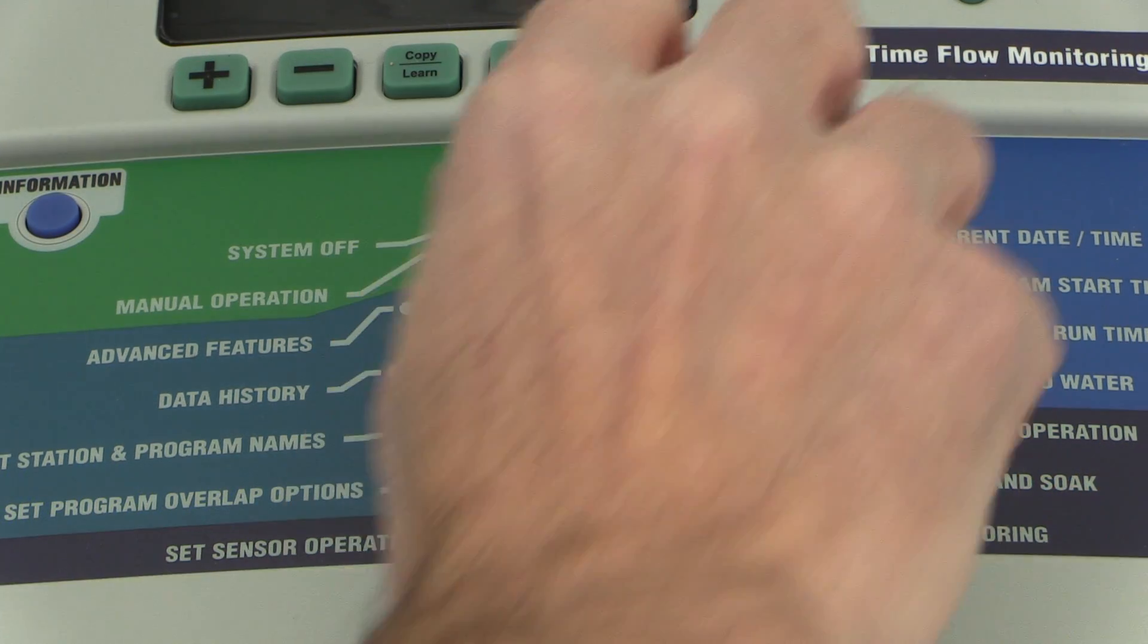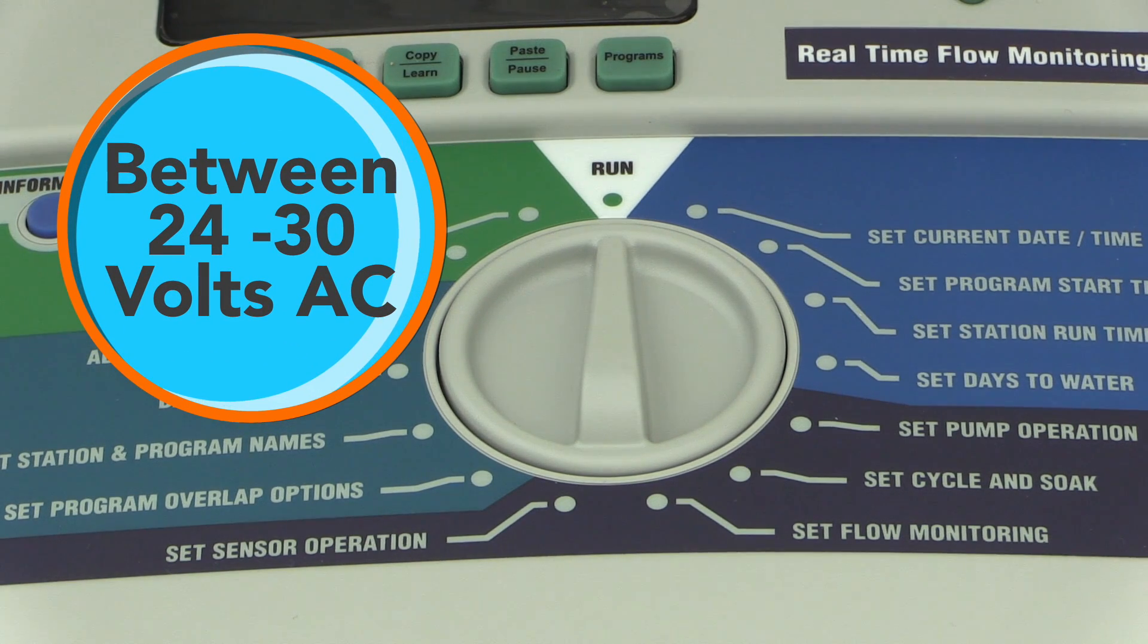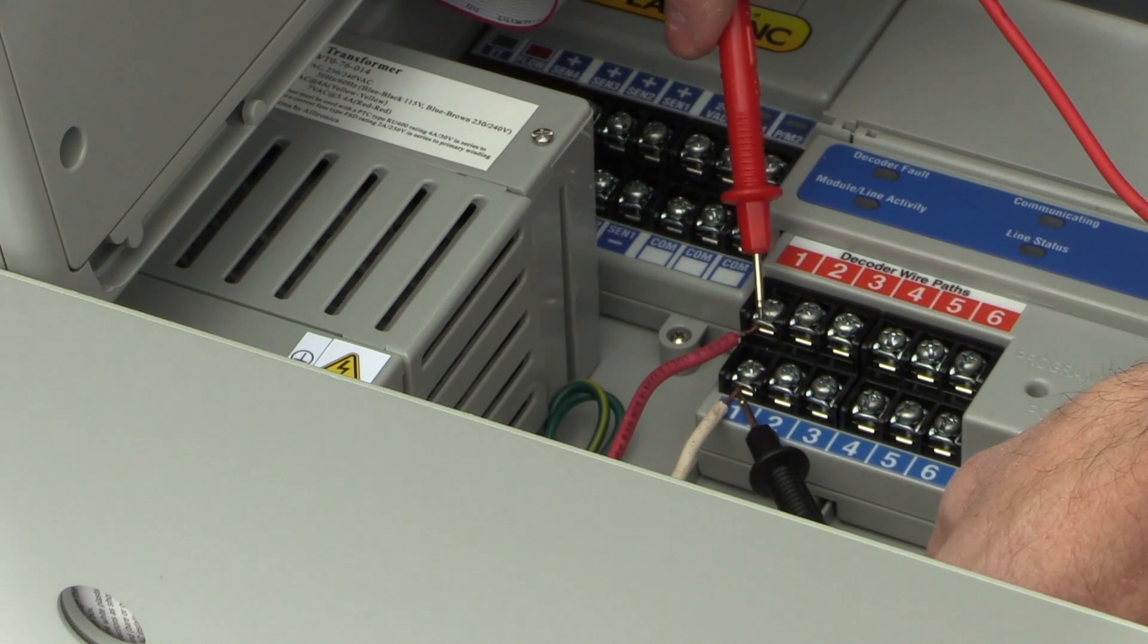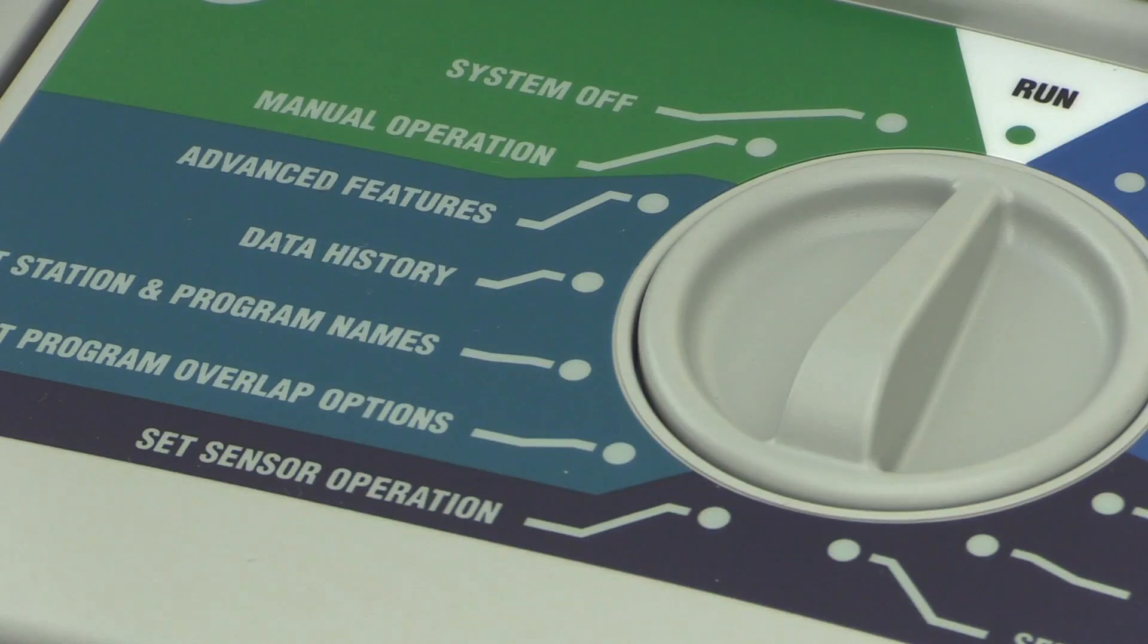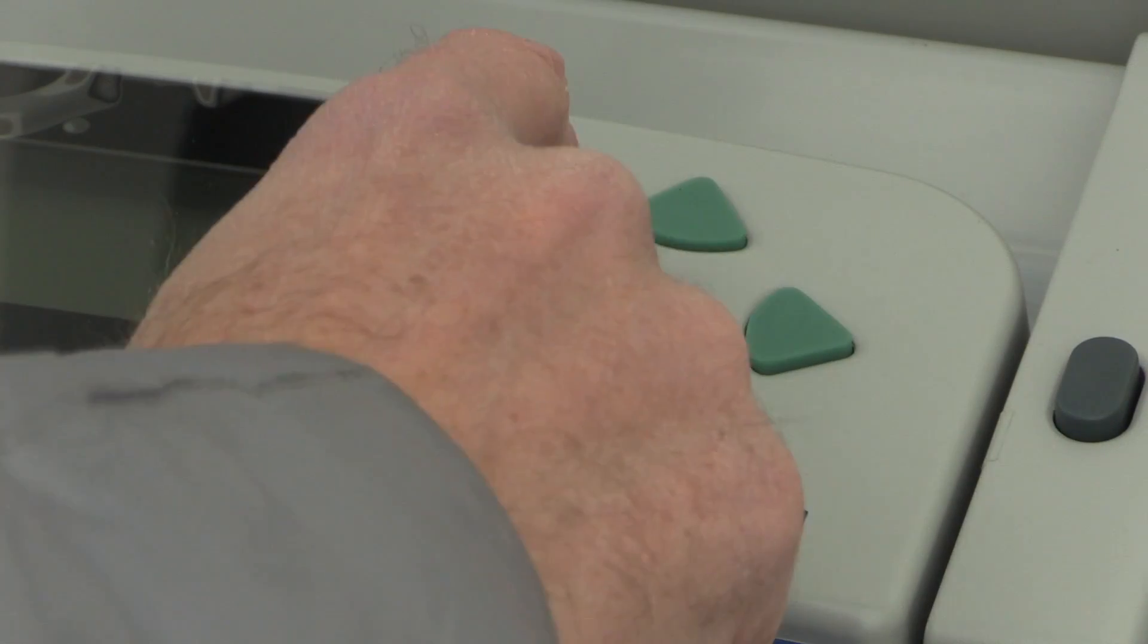With the system in run mode, the two wire paths should be energized with between 24 and 30 volts AC. You can read this output with the standard volt setting and the test probes. We will also assume you have eliminated any programming issues including setting up proper addresses for decoders at the main controller.